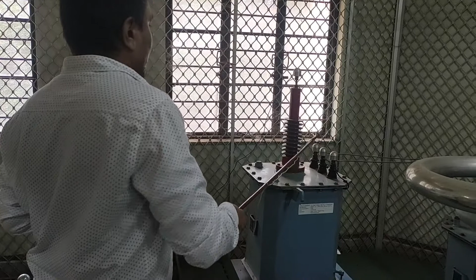Now after conducting the breakdown test, you should discharge the setup. This stick is known as a discharge stick, and here you can observe one wire is connected to this aluminum material, and this wire is properly connected to the ground. We need to discharge with this stick. Now why? Because we know that in the case of an air medium there is the presence of ionization, and secondary ionization is responsible for the partial discharge phenomenon, right? So in order to remove the partial discharge phenomenon as well as the presence of electrons over the surface of the HT electrodes, I am discharging the HT sides.